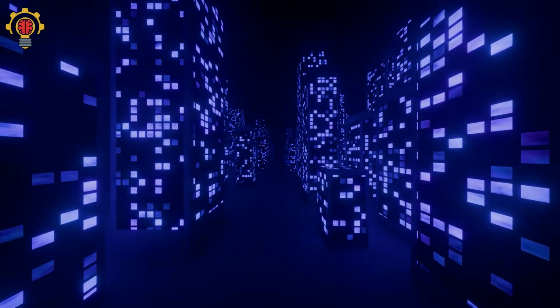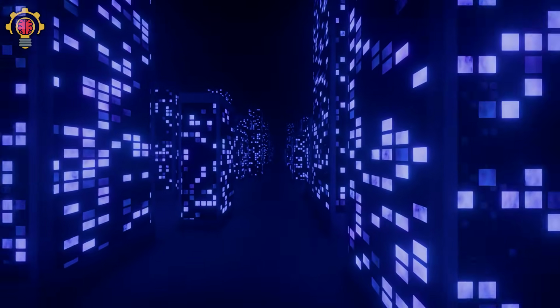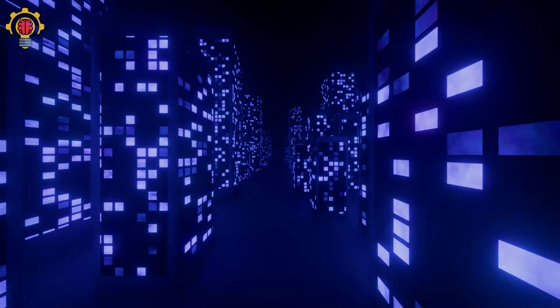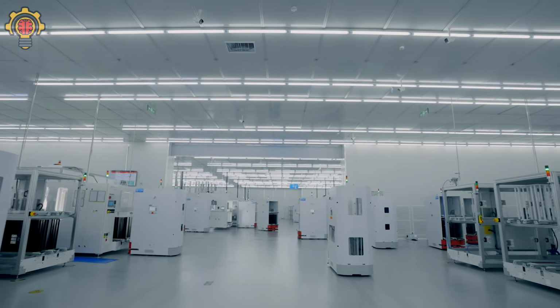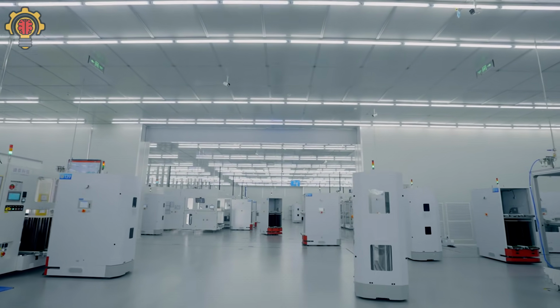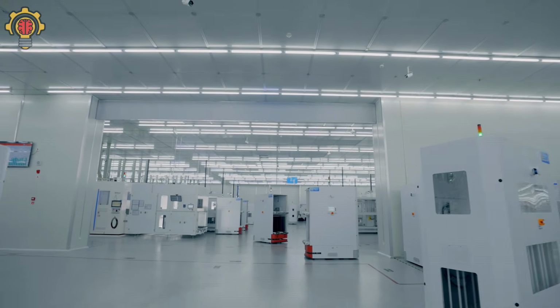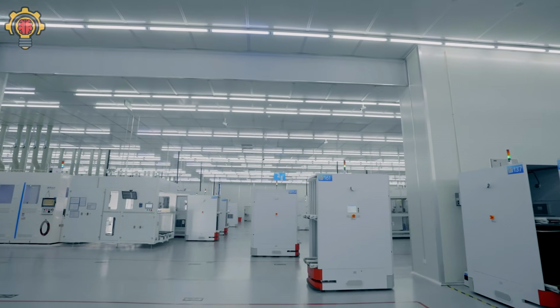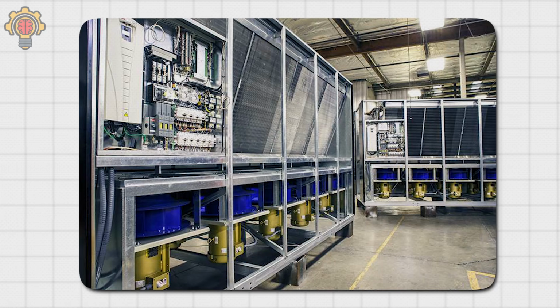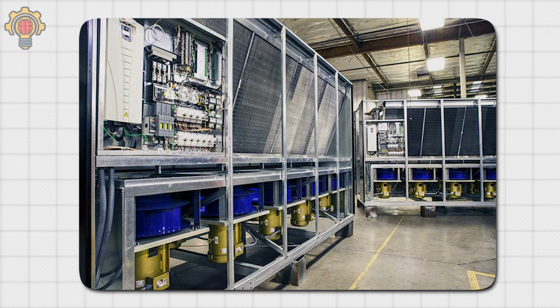For years, the most common cooling systems inside data centers were CRAC units and CRAH units. They may look similar from the outside, but they work differently. A CRAC unit, short for computer room air conditioner, uses DX cooling. Refrigerant absorbs heat from the air, then transfers that heat outside through condenser systems.